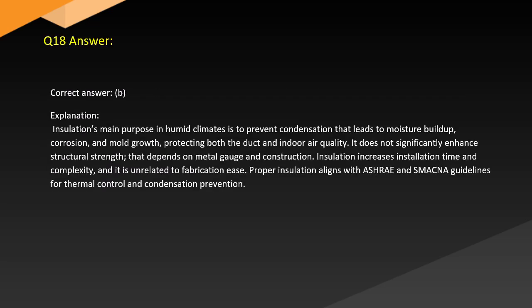Answer. Correct answer, B. Explanation. Insulation's main purpose in humid climates is to prevent condensation that leads to moisture buildup, corrosion, and mold growth, protecting both the duct and indoor air quality. It does not significantly enhance structural strength. That depends on metal gauge and construction. Insulation increases installation time and complexity, and it is unrelated to fabrication ease. Proper insulation aligns with ASHRAE and SMACNA guidelines for thermal control and condensation prevention.